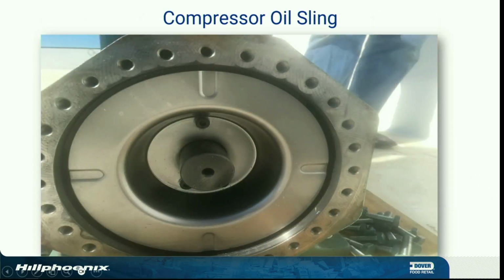All right, so Bitzer compressors. Everything less than a 40 horse does not have an oil pump on it. They use a slinger system. They've got these cups. As the crank turns, it slings the oil around the system to lubricate the bearings. We've got a hole right down the center of the shaft, and we'll have a cup at the end of the end plate. As the oil splashes into it, the centrifugal force of the crank turning will actually draw the oil down and get to our journals inside the compressor and keep them lubricated.